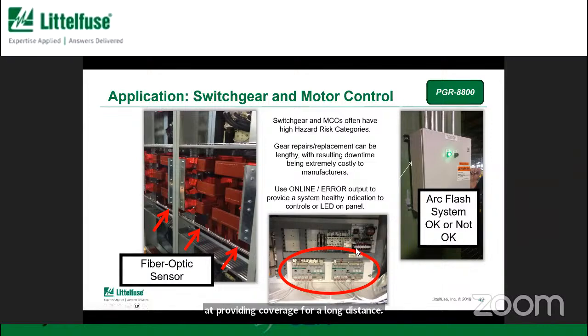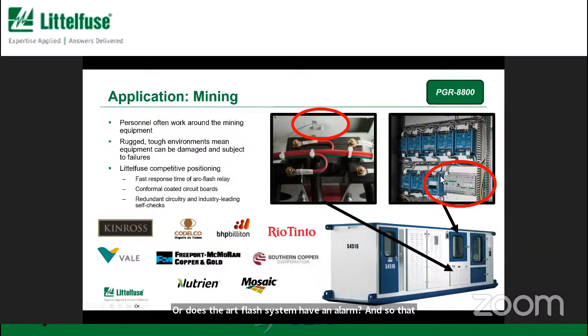And then in the control compartment, you have the arc flash relays here. So here's two PGR 8800s. And like I said, there's an alarm output as well, separate from the trip. You can use that alarm output to put a light on the front of the door to say, is the arc flash system okay? Or does the arc flash system have an alarm? That would give you indication of whether it's healthy or not.